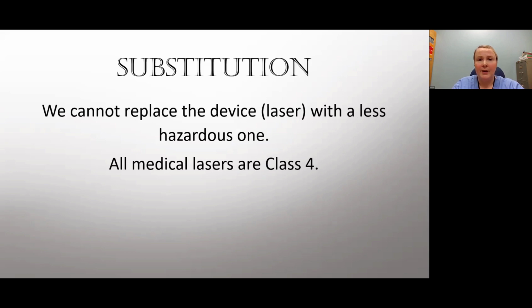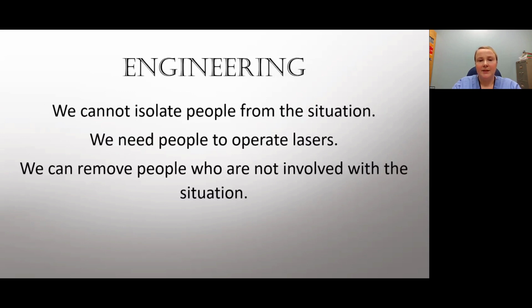Substitution, we cannot replace the device laser with a less hazardous one. All medical lasers are class 4. So class 4 lasers, we need to have this personal protective equipment on. We need to have it so we can do the procedure properly. All medical lasers are class 4, which means that any laser under that wouldn't be considered a medical laser. So you wouldn't be able to do a procedure with a class 3. Technically, some do have class 3 lasers, some towers, which are used for aligning scopes, things like that.